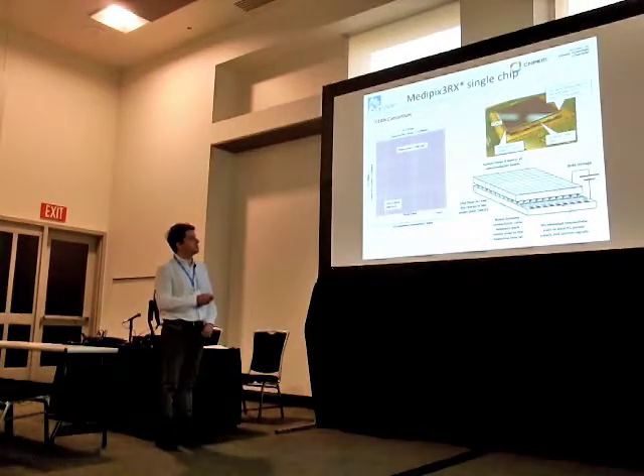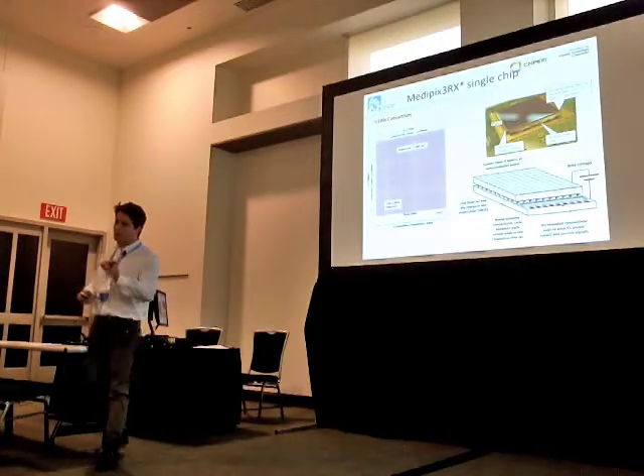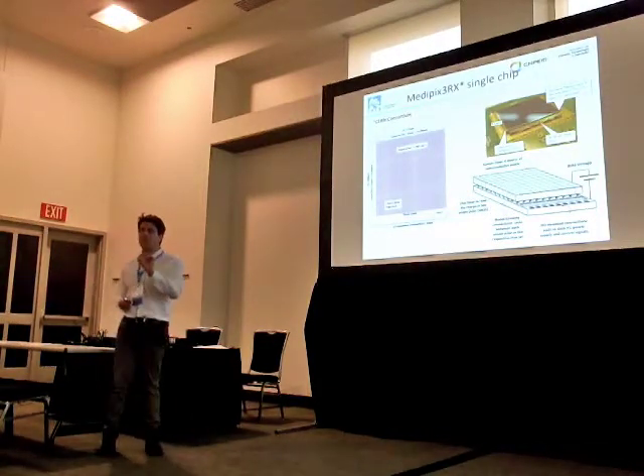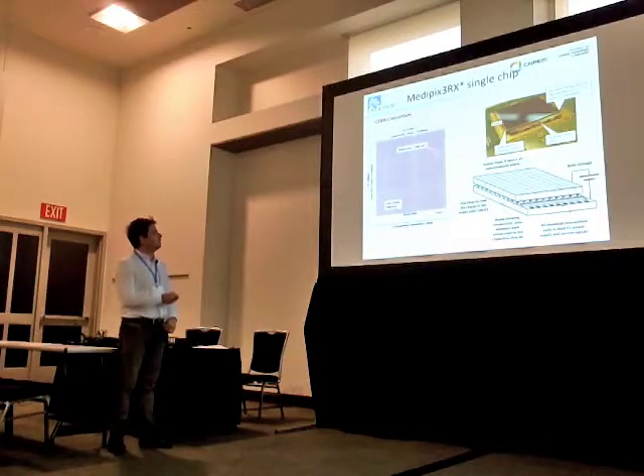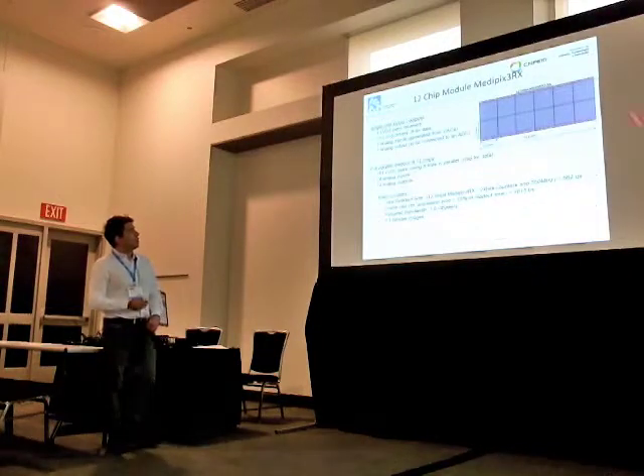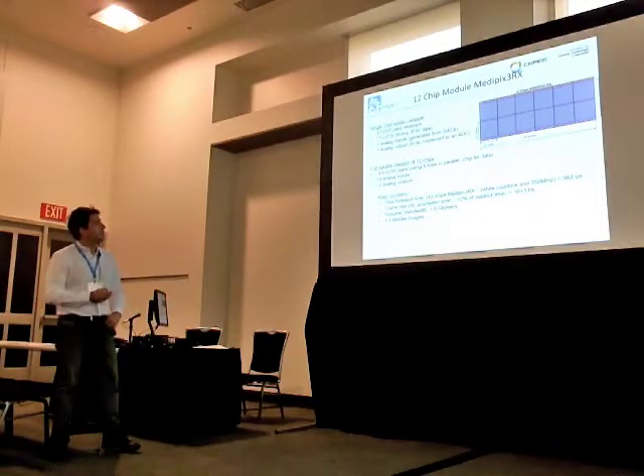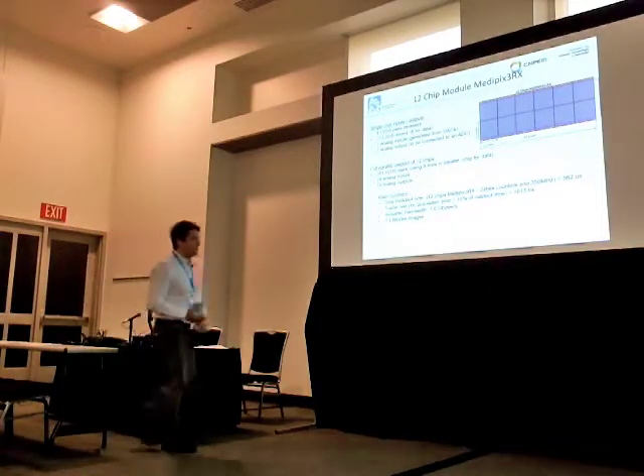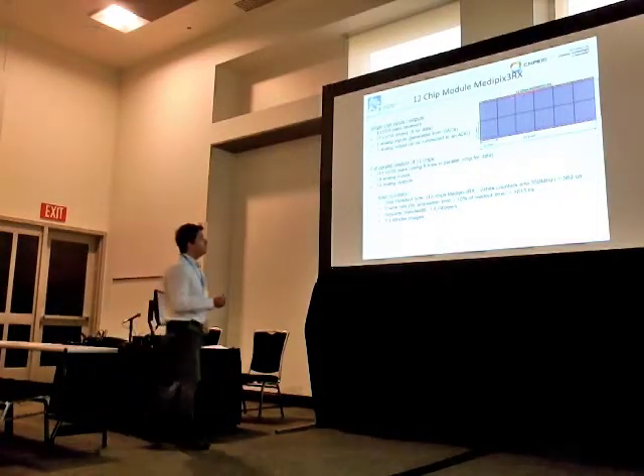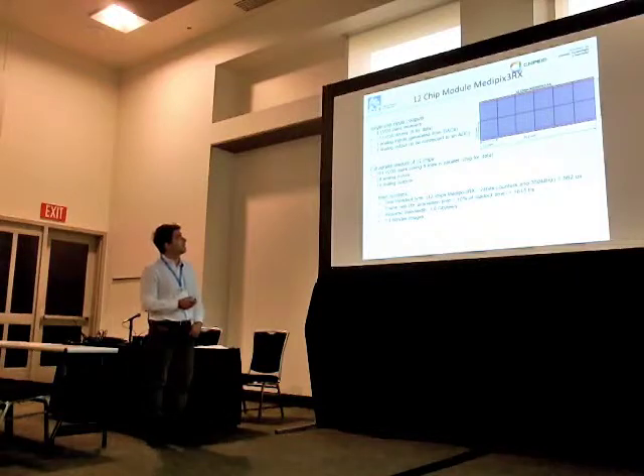And this is what this kind of very nice chip does. You basically have a sensor that converts X-rays into electrical pulses, and every pixel has its own digital and analog circuitry, built within 55 microns of size. And so the consortium provides these chips and all the connections and so on, and we started a project to integrate several of these chips. There are other projects I will mention briefly, to make a large area detector. So the goal is to make actually a large panel built from tiny sensors, but the consortium deals with the chip. We have to provide our own readout system for this large array of detectors.